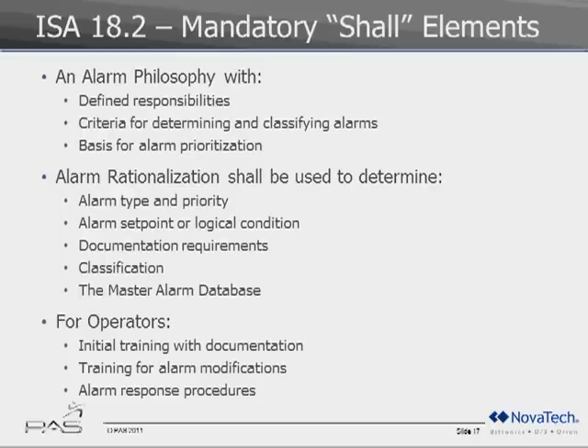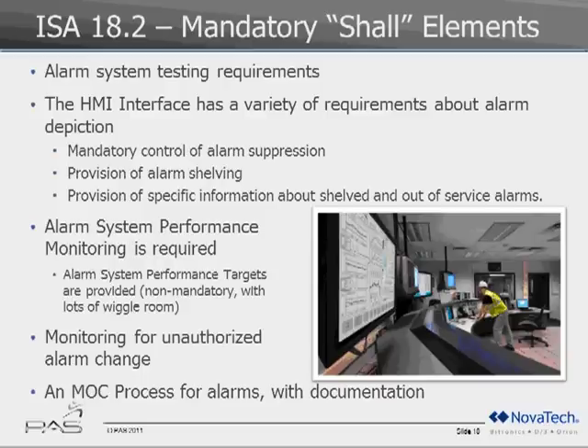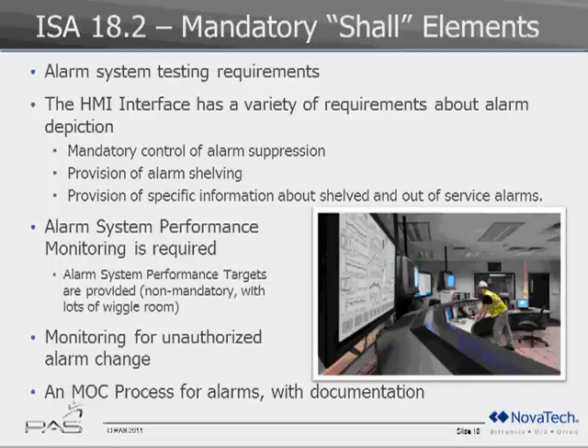Other shall components of 18.2 include operator training — just as in OSHA 1910.119 — so people are aware of and trained to respond to alarms. Additional shall elements cover testing requirements: how often the alarm system is tested, how alarms are depicted on the HMI, and provisions for shelving — a specifically defined term for temporarily taking an alarm out of service to avoid flooding the operator. Also included are performance requirements and an MOC process for changing alarm settings or disabling alarms.